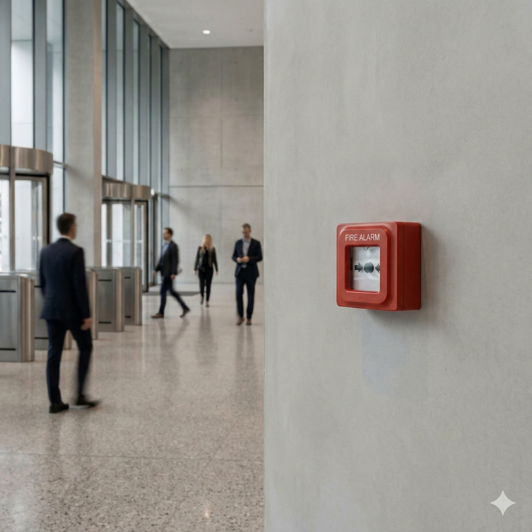And the wiring itself is also highly regulated. Right. The National Electrical Code, NEC Article 760. It's not just about fire code, it's about electrical separation. Exactly. It requires mandatory separation of the low-voltage fire alarm circuits from any line voltage circuits to prevent interference or faults from compromising the system. And the system isn't legally usable until it passes the structured commissioning process. It's a three-stage workflow. It is. It's the quality control gauntlet. You have pre-functional testing to check the basics: wiring, power levels. Then functional testing, where you simulate alarms and confirm the correct outputs occur.